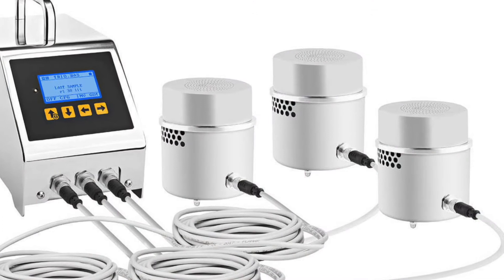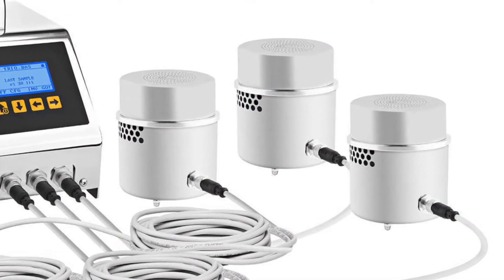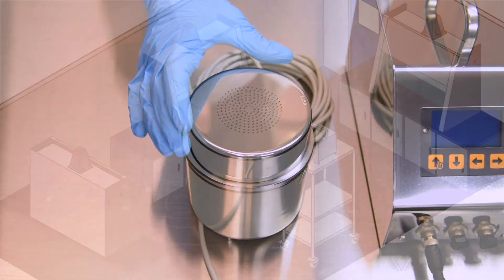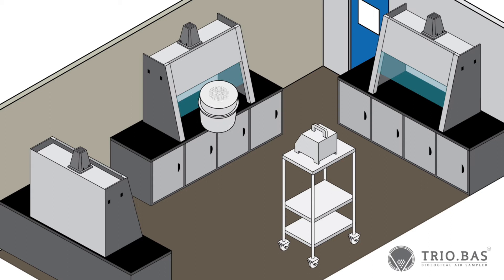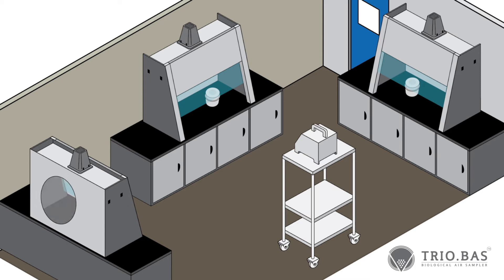The satellite design offers an innovative option for environmental monitoring. The independent aspirating chamber holds an agar plate and can be placed inside the aseptic processing area or at other designated sampling sites in the clean room.